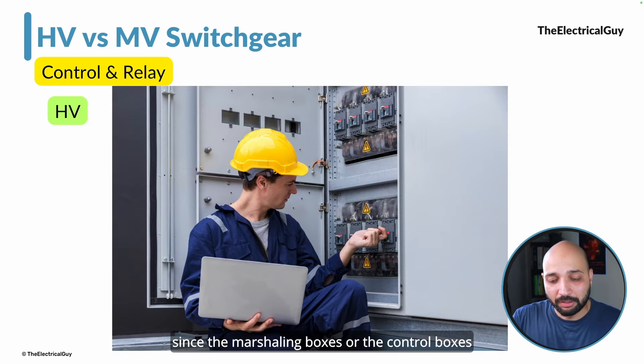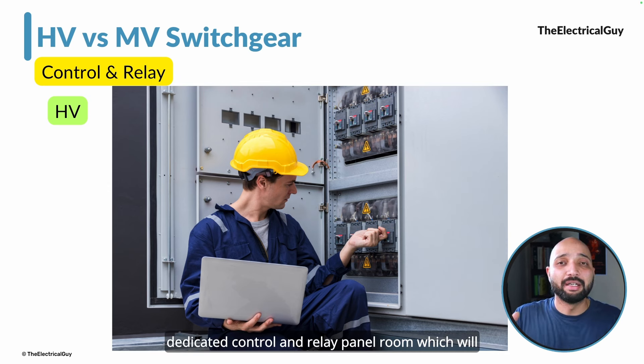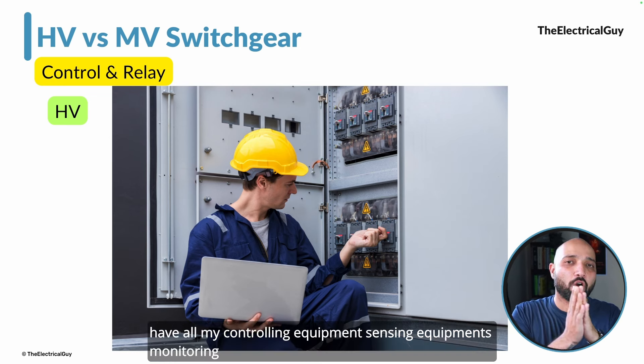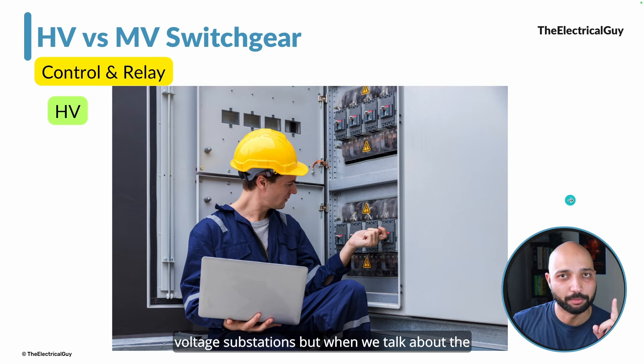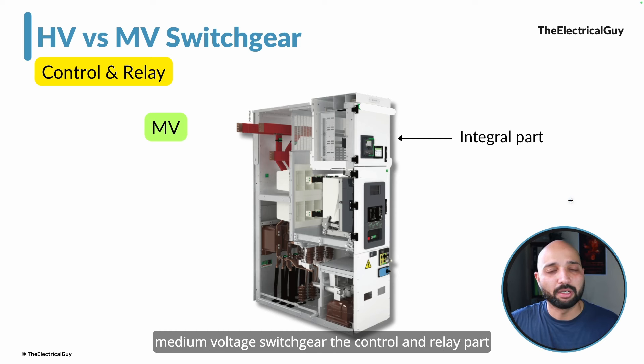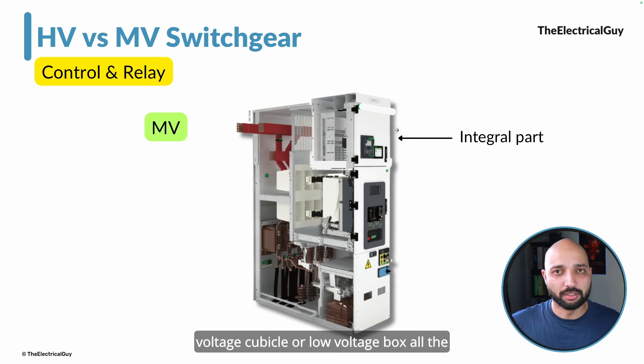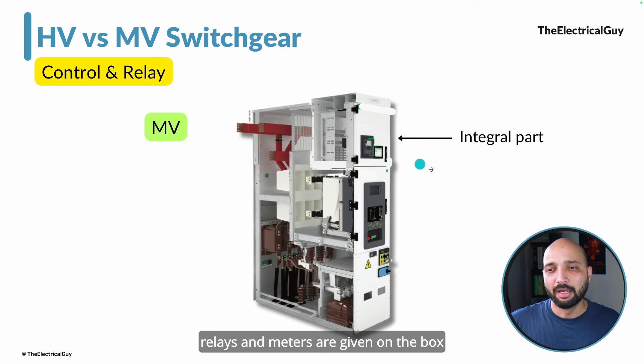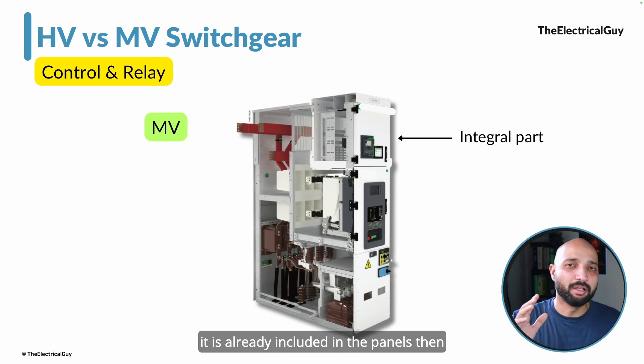In a high voltage AIS substation, since each device has a separate marshaling box, we need a dedicated control and relay panel room that contains all controlling, sensing, and monitoring devices. This is a requirement for high voltage substations. But in medium voltage switchgear, the control and relay part is an integral part of the panel — fitted inside the low voltage cubicle. All relays and meters are placed inside that box, so you don't need a dedicated control and relay room.